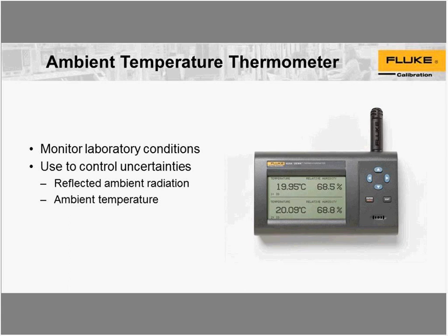For ambient temperature, you should have some way to monitor ambient temperature. Besides it being a requirement in ISO/IEC 17025, it also plays into a couple of uncertainties — these include reflected ambient radiation and ambient temperature.